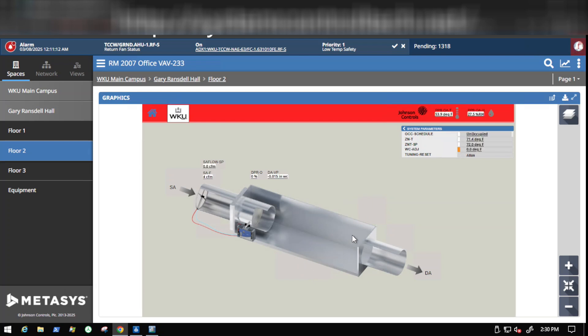If you do have completely different equipment, then that's something that you may want to do. This little display window here under the equipment summary is going to give you the option to select which one you want to look at. And you will see once again, that we have a bunch of equipment that is different and we do not have all of those points displayed here. So if you ever get into a situation to where you're building your equipment definitions, your equipment objects and all that, and you have similar equipment, don't worry about trying to set up a completely different equipment definition for that particular equipment. It is not necessary. You can simply set it up like you normally would. And then within your graphic, what does not exist will then simply not populate within your system.